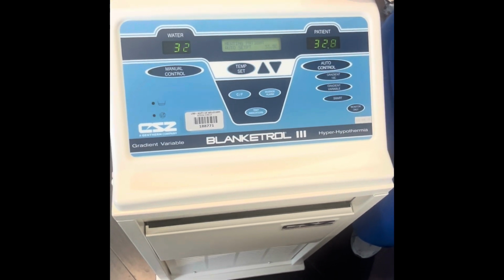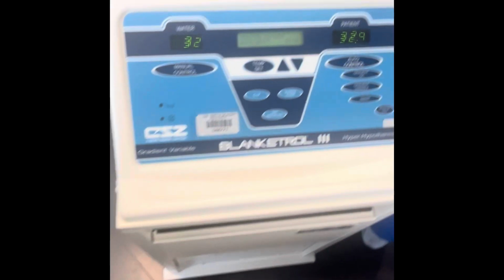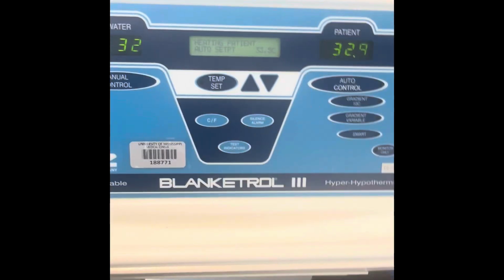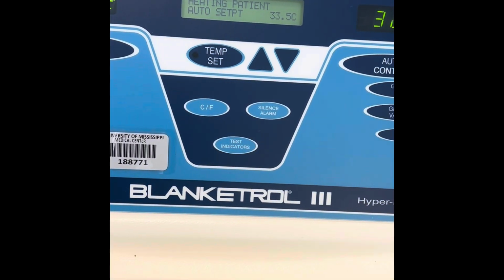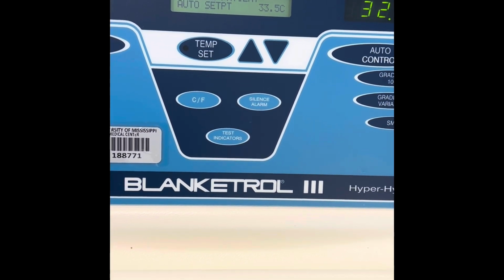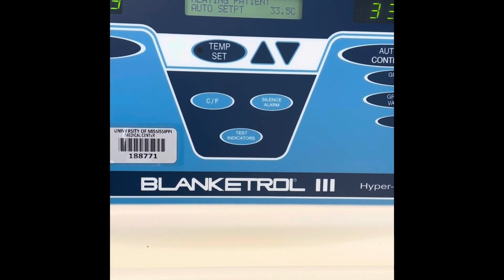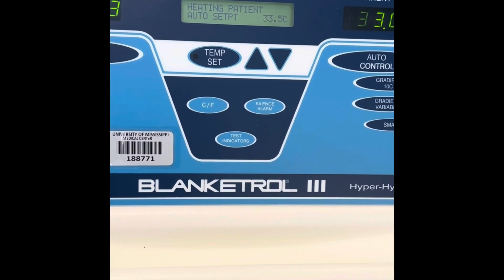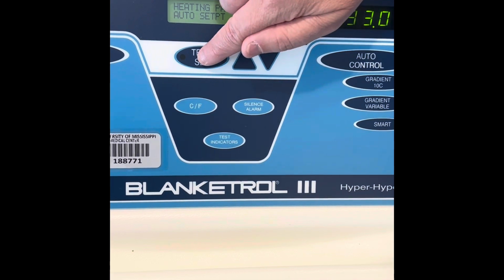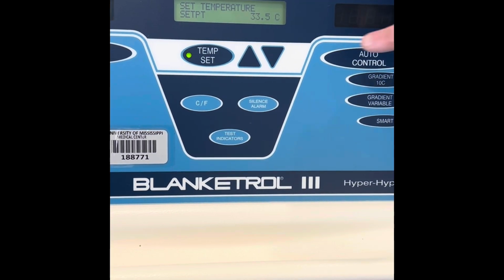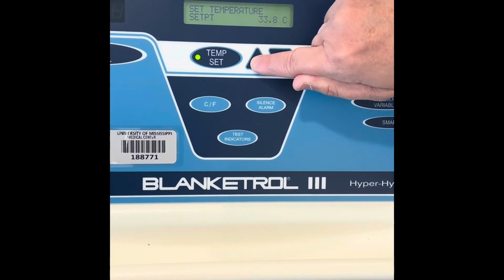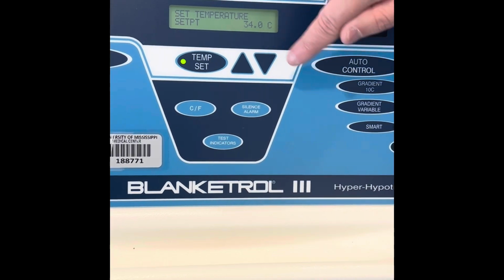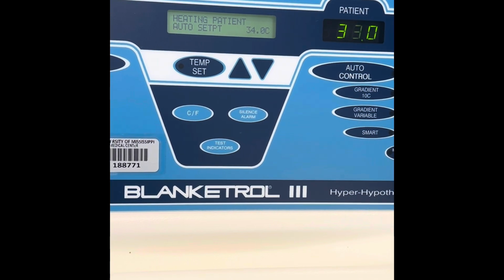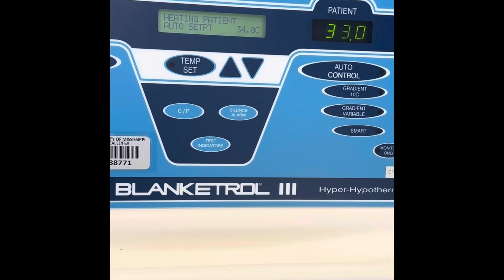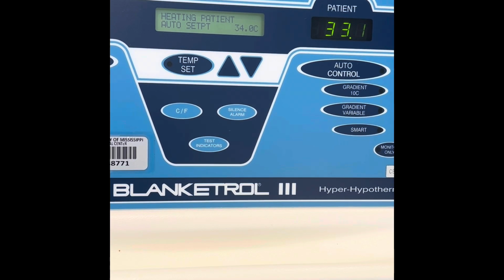Once 72 hours of whole body cooling is completed, you will start the process of rewarming. To rewarm, you will go to auto mode by hitting the temp set button. You will increase the set point temperature by 0.5 degrees Celsius every hour until you reach a temperature of 36.5.